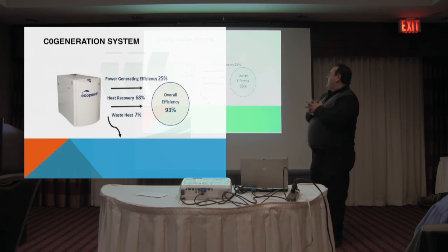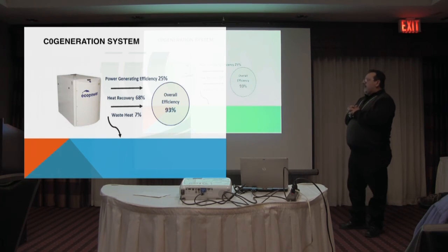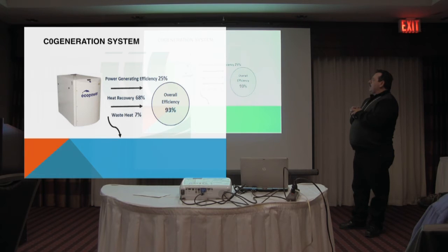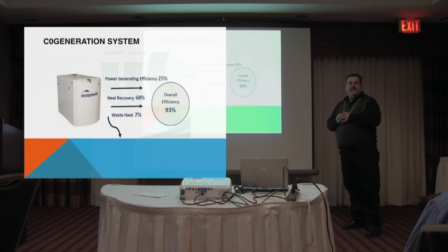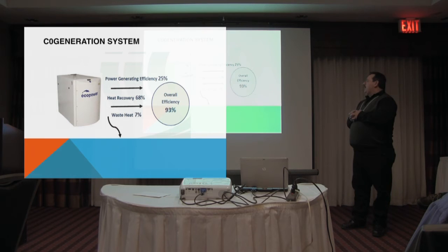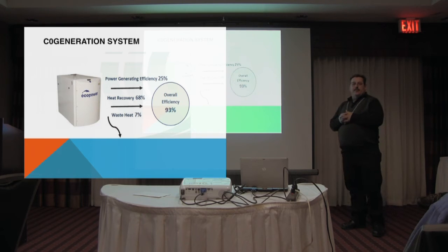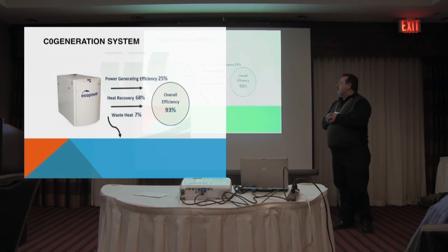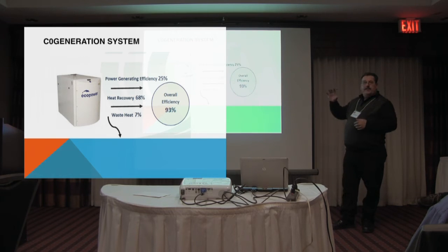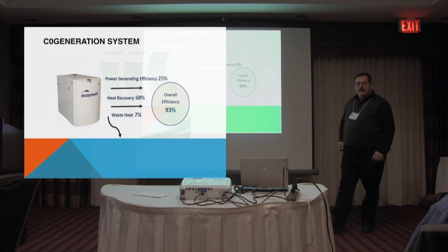So if we look at a cogen system, we have to look at combined efficiency. Looking at power generating efficiency on one product: it's 25%, heat recovery is 68%, and waste heat is 7%. So the combined or overall efficiency is considered to be 93%, where you're able to use that 93% of the total energy being produced within the building.